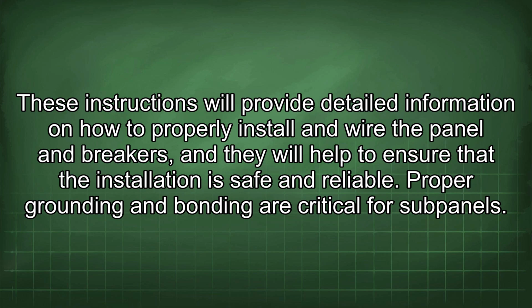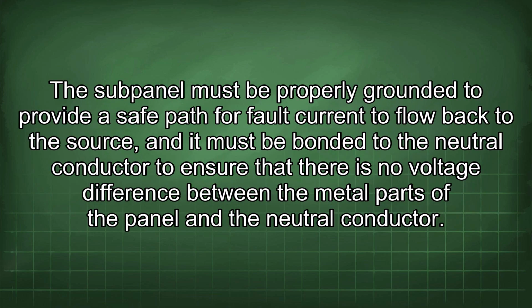Proper grounding and bonding are critical for subpanels. The subpanel must be properly grounded to provide a safe path for fault current to flow back to the source, and it must be bonded to the neutral conductor to ensure that there is no voltage difference between the metal parts of the panel and the neutral conductor.